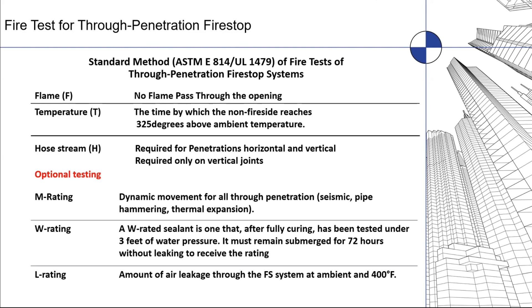And then an L rating is an air leakage rating, but generally speaking, that L rating is used for the passage of smoke or toxic gases. So if air doesn't get through, then smoke and toxic gas do not make it through there. And so there are all these different kinds of ways that they check to ensure that this works. Another type of test that's done in fire stopping is acoustic tests. Most fire stopping has some kind of acoustic rating as well, because if you have a floor or a wall that has openings or joints in it, you don't want sound just transferring freely through those openings.